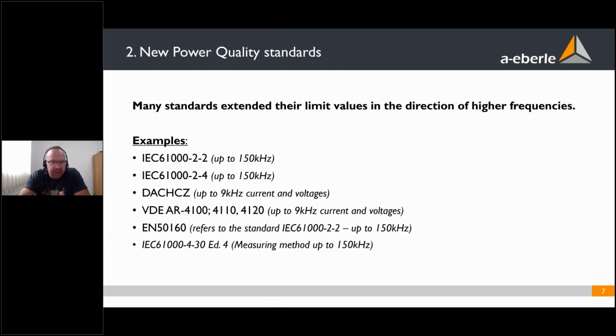Many standards react and establish limits up to 150 kilohertz. So we have a problem. We produce more and more superharmonics, and now we also need limits in the normal standards. One of the standards I often use is 61000-2-2, and here we have limits for superharmonics since 2018 up to 150 kilohertz.